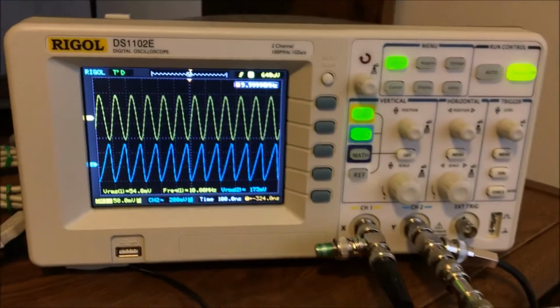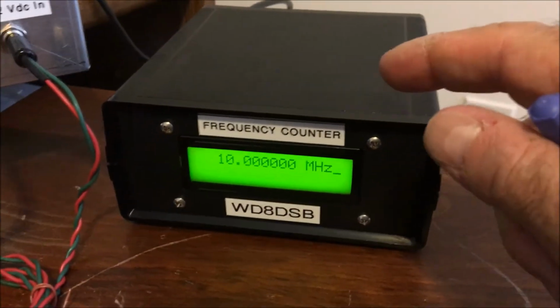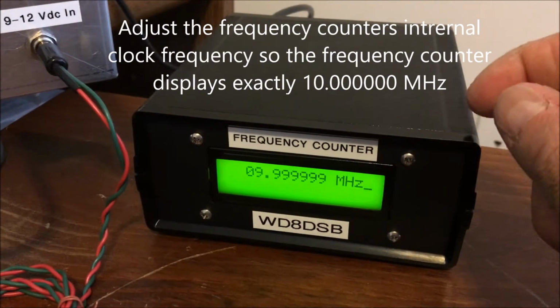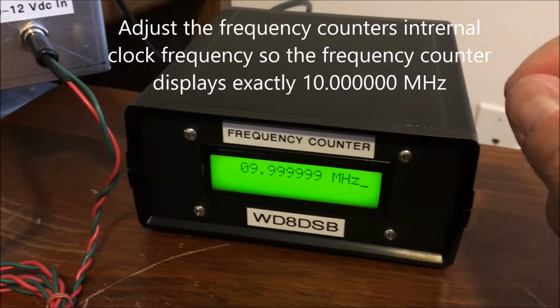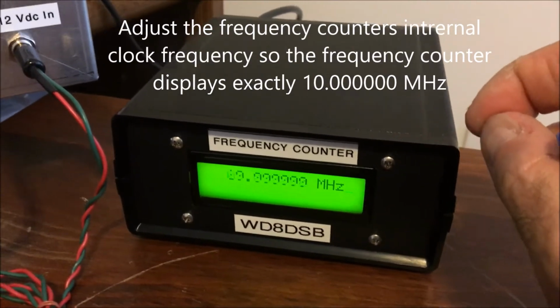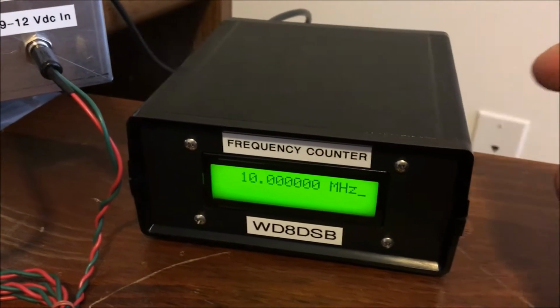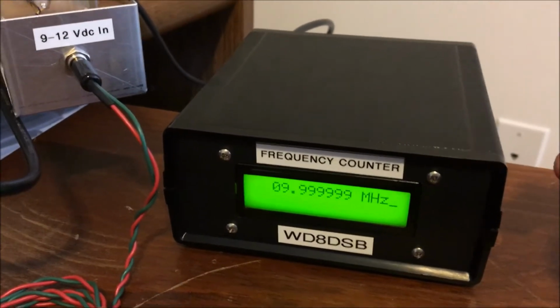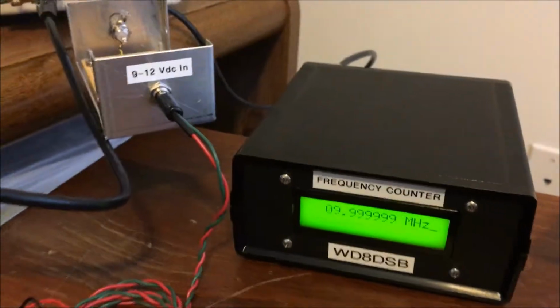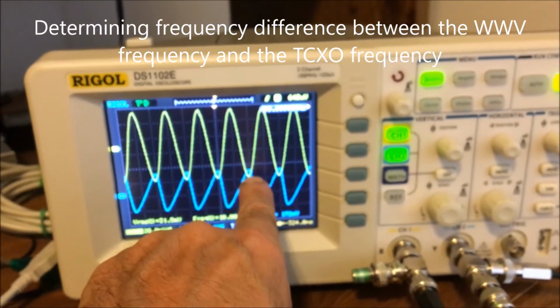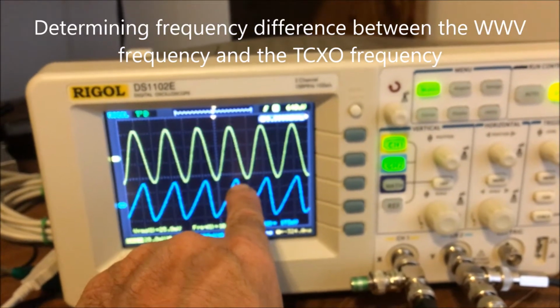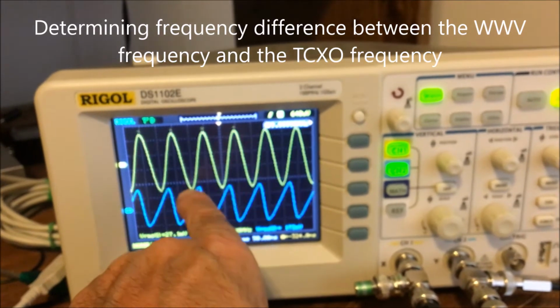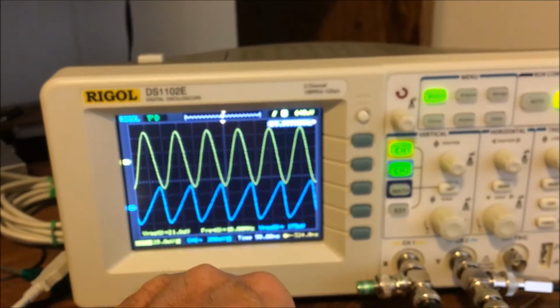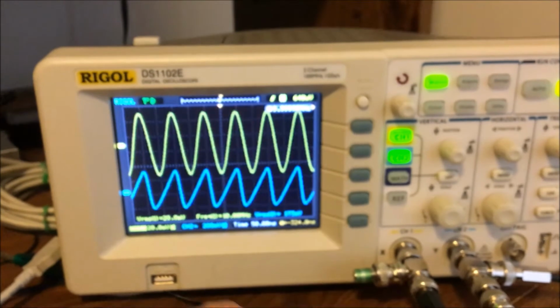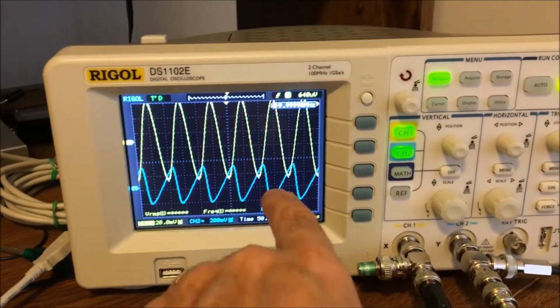Since the blue waveform is stationary relative to the yellow waveform, at this point I would go and actually calibrate the frequency counter internal clock, adjust it so it displays exactly 10 megahertz, which I've already done, and that's why we're so close at this point. Count how long it takes for this blue peak to move from one yellow peak to the next yellow peak. That gives us an indication on how far off in frequency we are. So we're going to go ahead and do that.